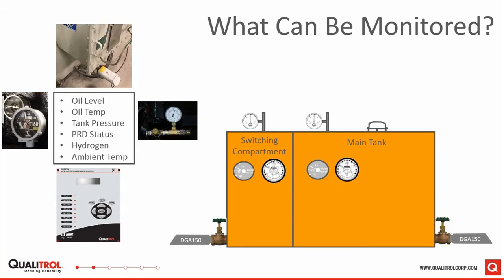At the top, in the top picture, we have one of our DGA150s, so that is monitoring hydrogen in real time. Typically, vault transformers have two oil compartments, one for the switching compartment or the primary switch, and the other one is the main tank. Due to the separate oil compartments, you need to monitor the hydrogen in each compartment individually. Therefore, the diagram on the right shows that you can install DGA150s on each of the drain valves for each tank. And then the picture at the top left shows a DGA150 installed on an actual transformer.